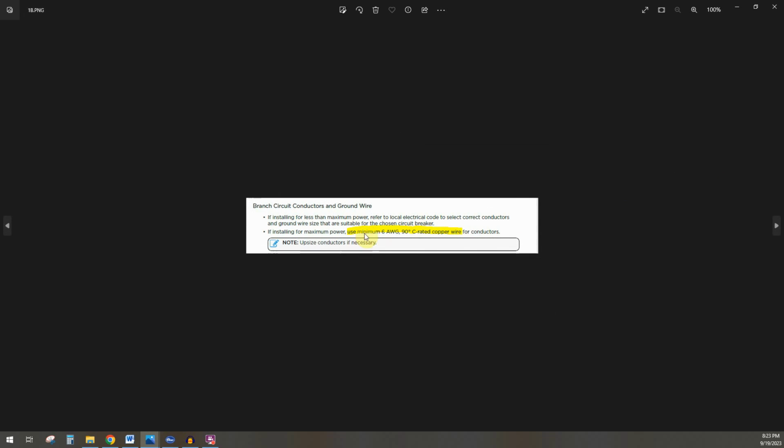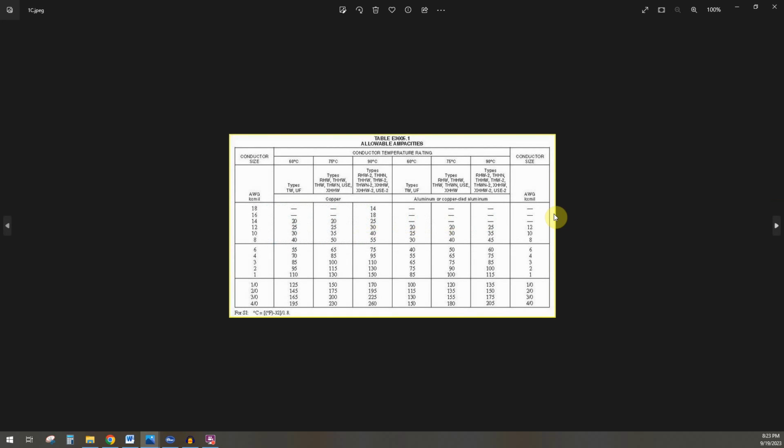And as you saw earlier, Tesla recommends 6-gauge AWG at 90 degrees. So if we're looking at the chart, 90 degrees, THHN is right here. It's right at 75 amps, so you're good. So just keep that in mind. Now, the reason why there's a big debate is because of this 55.